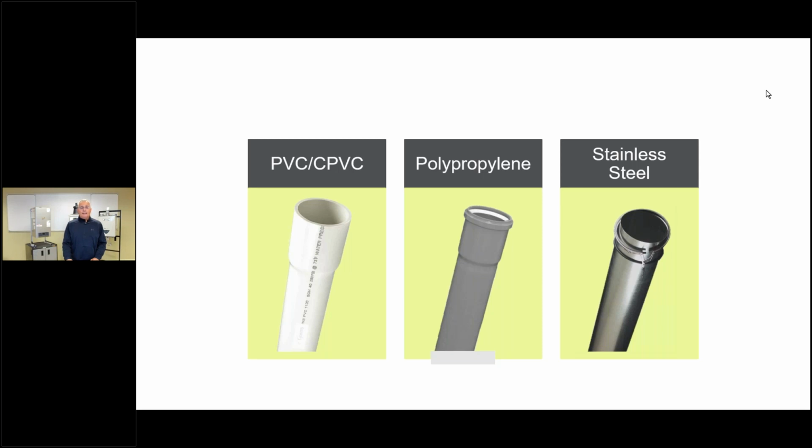Go on any manufacturer of PVC's website and try to find a white paper that'll explain or give you temperature ratings. They do not exist. All right? They don't exist. So this is not material meant for venting. Again, I could use it as long as I'm keeping within that 140 degree temperature. That means, again, your supply water temperature, you're talking is 120.